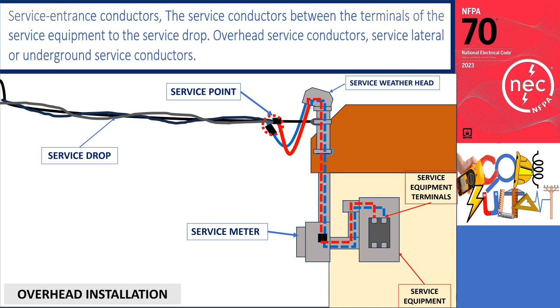How about service entrance conductors? These are the service conductors between the terminals of the service equipment and the service drop, overhead service conductors, service lateral, or underground service conductors. In the provided illustration, there is a depiction of a service entrance conductor that is connected, at the point of attachment, to service drop conductors. These conductors run down the side of the house, pass through the meter socket, and ultimately terminate at the service equipment.